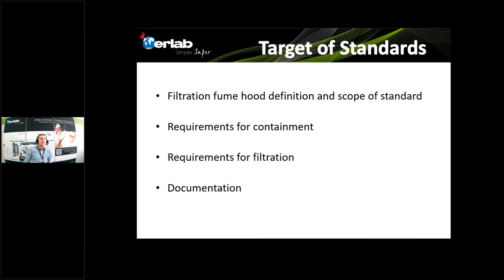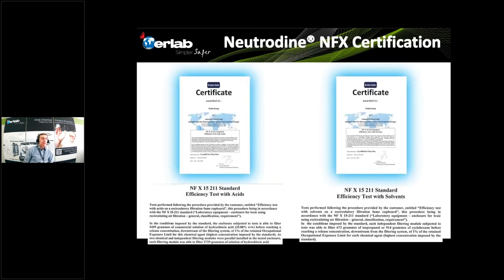The targets of each standard are the same: filtration requirements, containment requirements, and documentation. All fume hoods complying with the standard must be labeled with a sticker referring to the standard. I also recommend asking the manufacturer to provide a certificate of test by a third party. At Erlab, all our products are tested by ENTERTECH and AirFly Concept for containment and filtration.